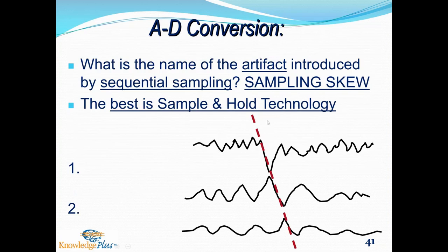There's a feature on EEG machines called sample and hold technology. It's the best digitization method. If you don't have sample and hold technology, but rather are using sequential sampling, you're going to introduce sampling skew, where the first channel and the last channel aren't time synced, which could make a spike look like it's not phase reversing at the same time.